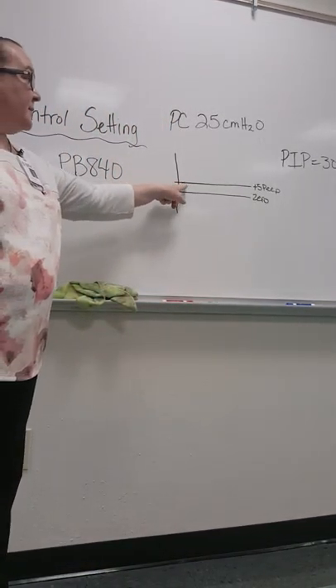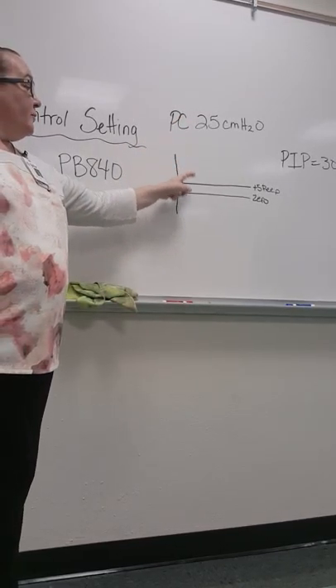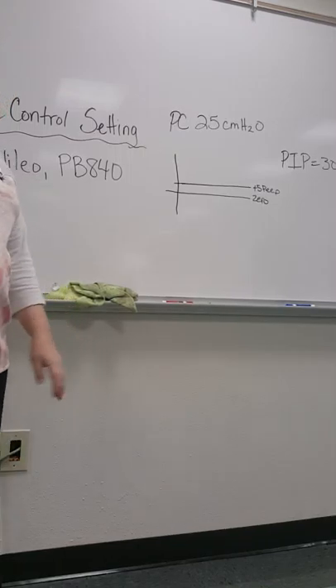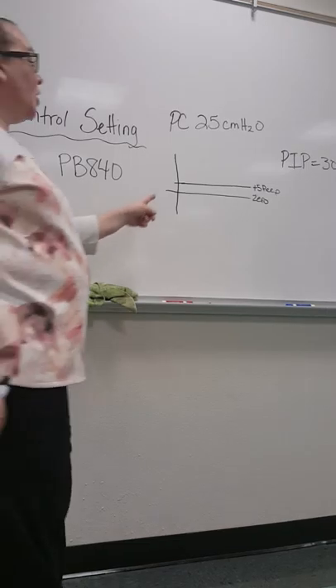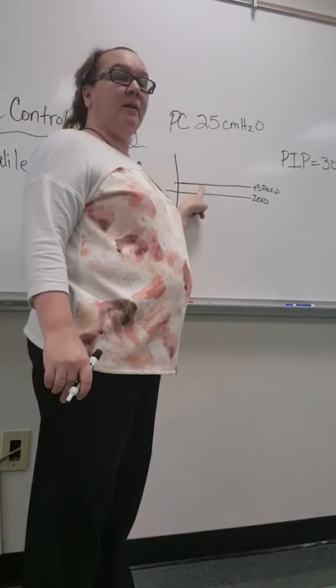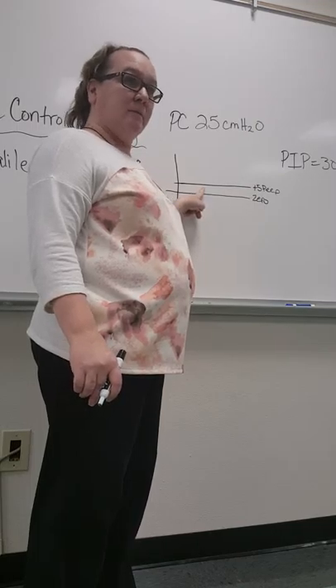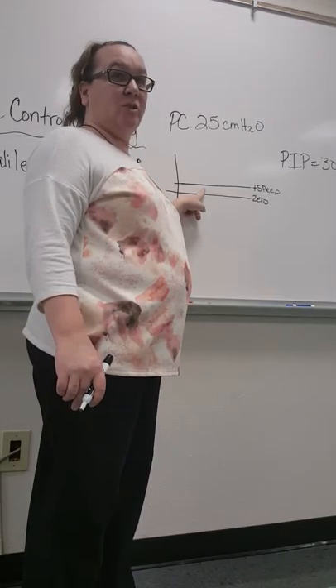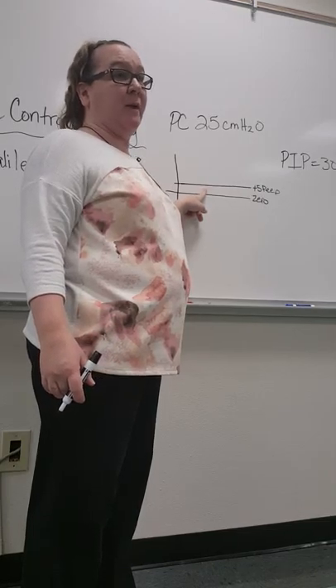The same starting settings and the same pressure control. 5 of PEEP and 25 of pressure control. The problem with the Dräger is even though we have 5 of PEEP there, the Dräger brain doesn't realize it's there. So it's called not PEEP compensated. It doesn't understand that there's a PEEP there.